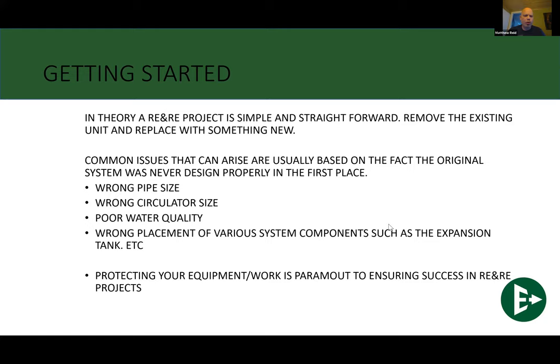Maybe you're over pumping, you're undersizing. Wrong pipe size is actually the biggest one that I see, bar none, compared to any of them. Poor water quality, where you're talking about a tremendous amount of sludge going through the system, or you've got a lot of scale buildup already. And then the wrong placement of various systems and components, such as the expansion tank. That's, again, usually a big one that I see.